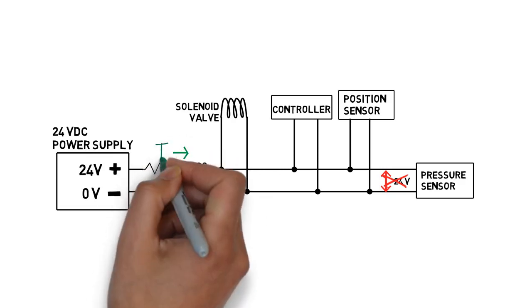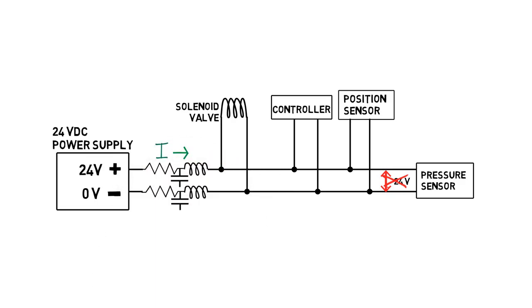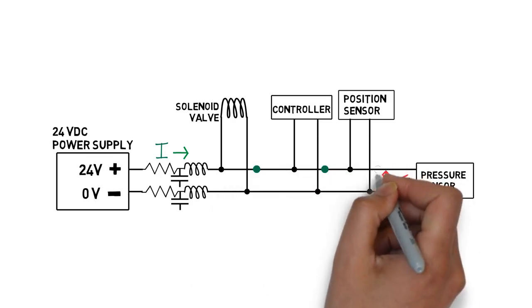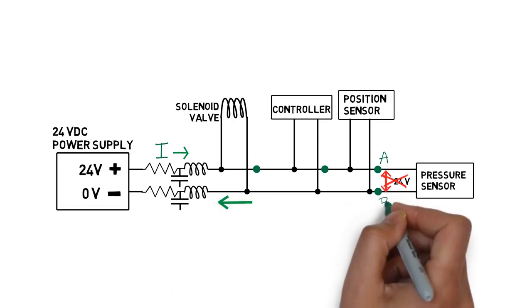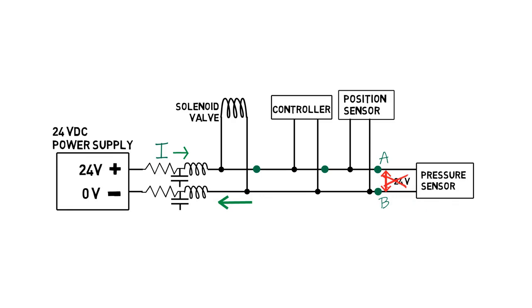This means that when a current flows, the voltages at various points in the wire are not the same. In our example schematic, if we have a current in the wire, the voltage at point A will now be less than 24 volts. The current also flows back to the power supply, so the return wire will have a different voltage, meaning that point B will be more than zero volts.